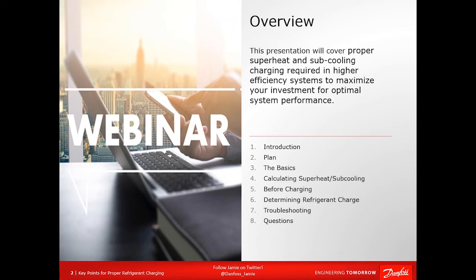The reason I put airflow first is because if your airflow is incorrect, nothing else really matters — nothing is going to have a correct value. You can use the most accurate equipment, whatever charts you want; if your airflow isn't correct, nothing else matters. On top of that, the refrigerant charge determines the value of key parameters in the system, which control the absorption and rejection of heat. For the system to operate as designed, these heat exchanges have to happen at certain temperatures. And refrigerant charging is the one variable you are in direct control of.